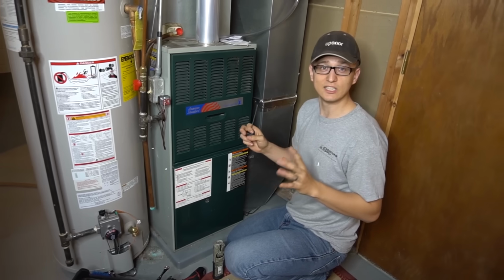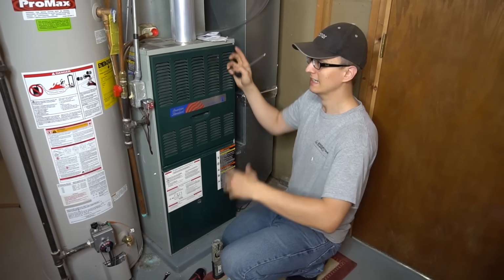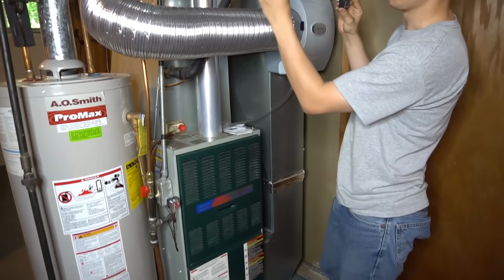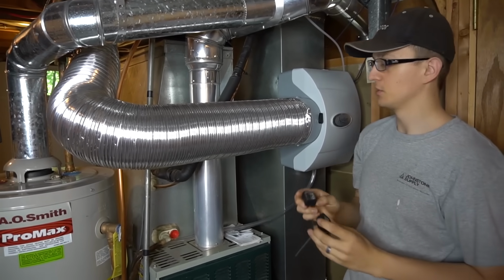Also, if your AC is working but you think it's not cooling quite well, everything seems to be working. The fan's working inside, the outside unit's working. It seems to be cooling but not quite there. What you can do to check that is measure the temperatures in your supply trunk and your return. If you would like, I actually have a video explaining how to do this as well. I'll put that in the description below.